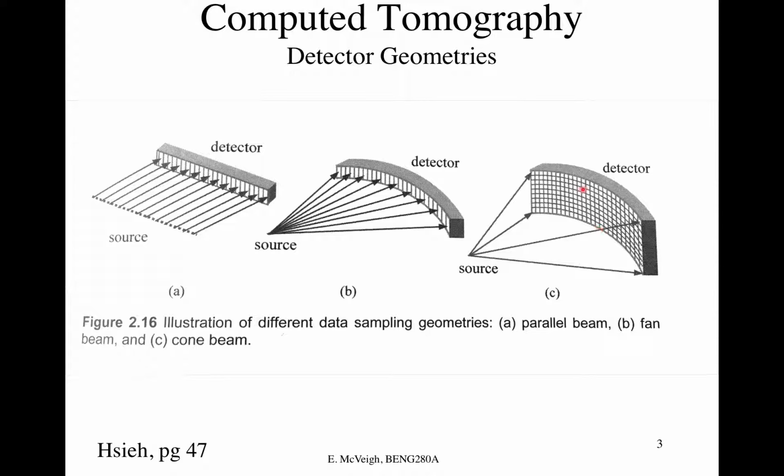So you can just combine every two, and all of a sudden your sampling rate is cut in half, right? And the estimate of the number of X-rays you're getting is improved when you combine two together because you're averaging, right? But you get a blurrier picture. So that's true. You can drop the sampling rate.